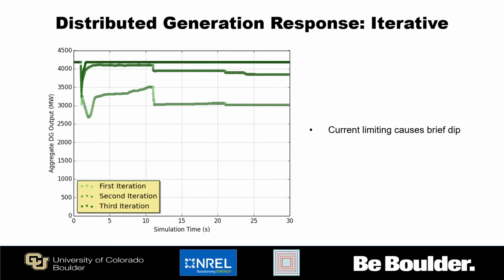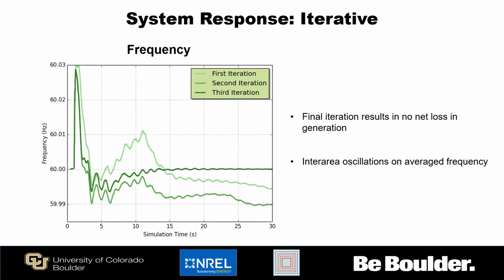a brief dip in the DG output. So this is the momentary cessation of 1547, but then that does improve over time. And as we iterate through, we see that there are corrective actions that can be taken that can prevent that voltage dip from causing a more sustained reduction in the DG output.